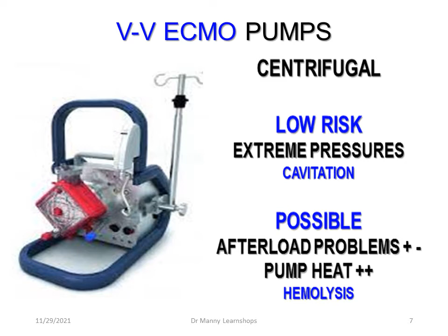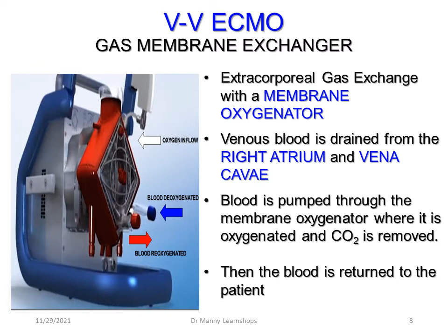Venous blood is drained from the right atrium and the vena cava, as we've indicated previously with the cannulas. So this is blood that is low in oxygen. SvO2 is low. The blood is pumped through a membrane oxygenator where it is oxygenated and CO2 is removed. Then the blood is returned to the patient. That's the function of the VV ECMO gas exchanger. Oxygen inflow, deoxygenated blood goes in, blue port, reoxygenated blood comes out, red port, from the gas exchanger, or the membrane gas exchanger, or the diffuser, whatever terminology you choose to use.